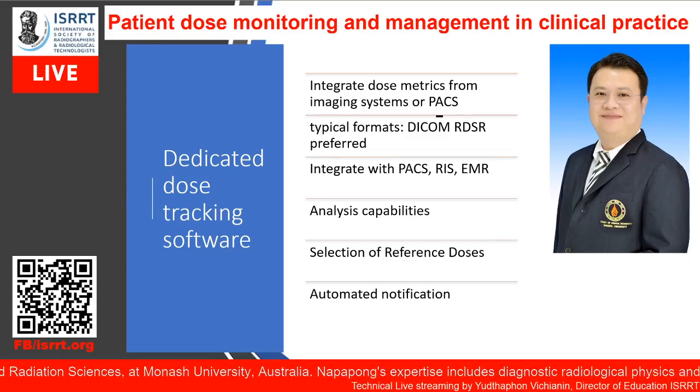And this software mainly integrates with PACS, RIS, or EMR. It has analysis capability. You can select a reference dose so that you can monitor, you can quantify the dose, and you can give alarms to the staff about high dose that happens in your facility.